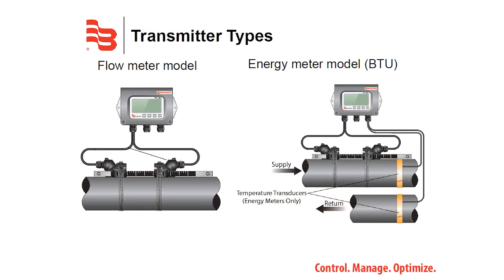There are two main transmitter types with the TFX Ultra. It can be configured as a basic flow meter transmitter to give a volumetric reading output. Alternatively, it can be configured as a BTU metering system, which includes transducers for flow and temperature for use as a hydronic heating and cooling system. The TFX Ultra carries hazardous rating certifications of Class 1 Division 2, with options for Class 1 Division 1 through the use of intrinsically safe transducers.